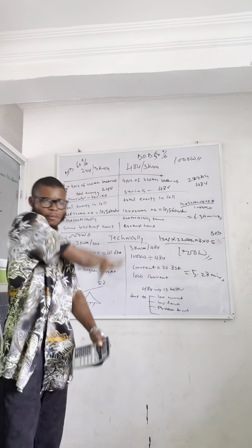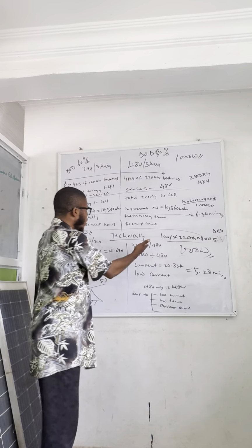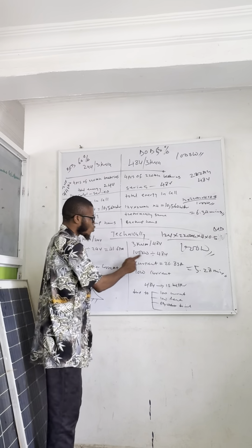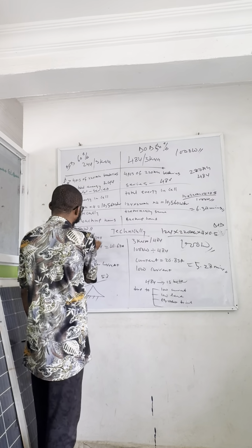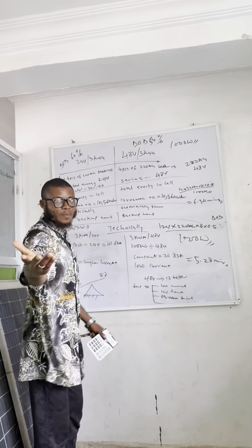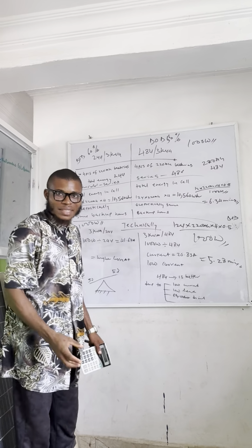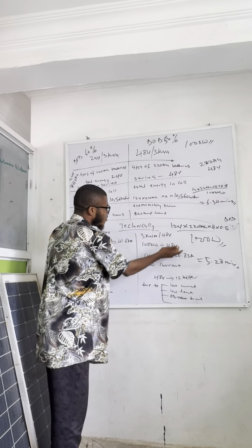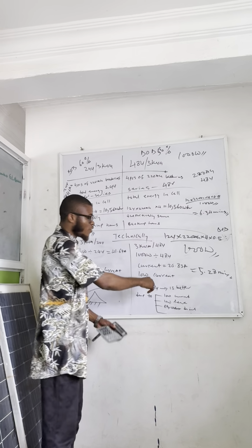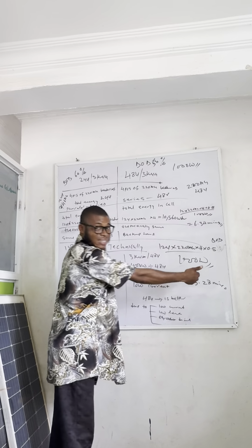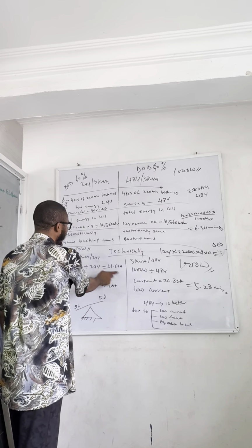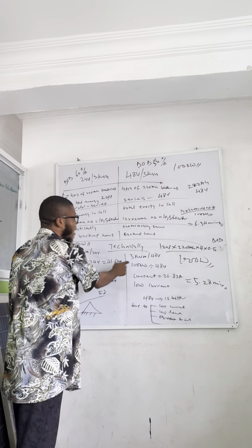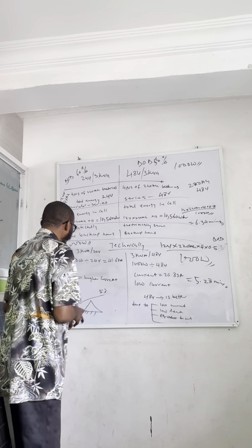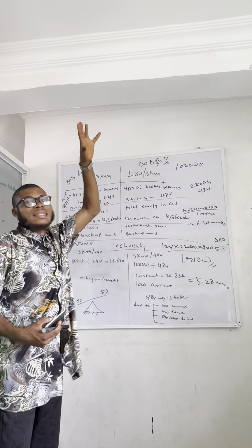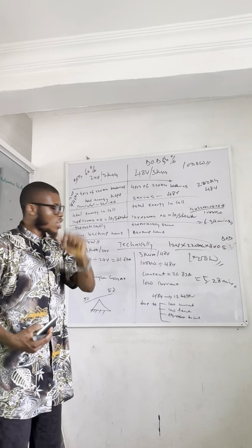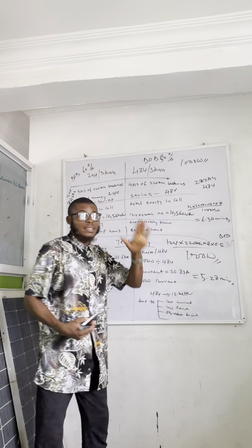Now let's go back. Technically, our 48 volt system will be running with a 1000 watt load, and our 24 volt will also be running with a 1000 watt load. The current which they are going to be discharging, let's take a look at it. 1000 watt load divided by 48 volts, you have 20.83 amps. Likewise, 1000 watt divided by 24 volts, you will have 41.67 amps, which means your 24 volt will be discharging at a higher rate, higher current. That is what I mean. And why will this one be discharging at a low current?